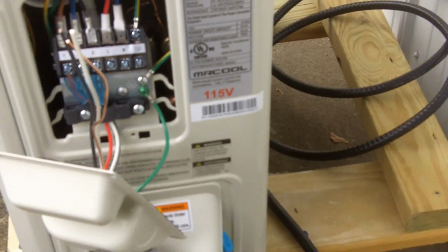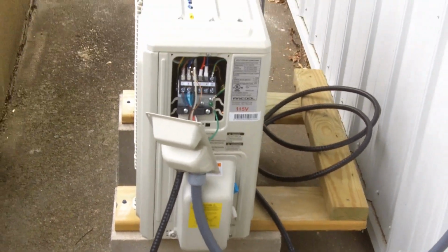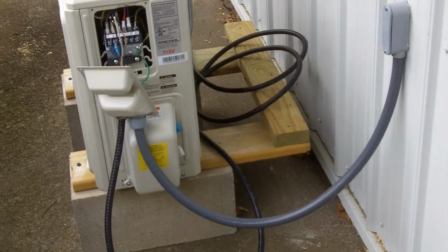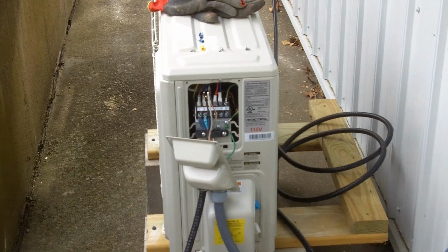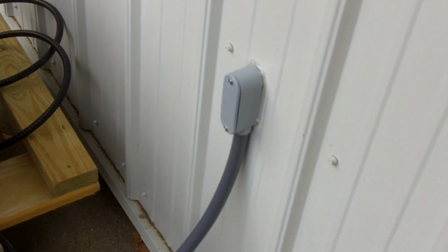You have to take off a green screw on the bottom right for your ground wire, and then the other 3 plug right in. Here I'm showing where the 2 conduit connectors come in - that's from the indoor unit, the green ground, and then there are numbers you can't really make out here, but 1, 2, 3. Make sure you're on 1, 2, and 3 corresponding with the indoor wires, which have 1, 2, 3 written on one side. Just make sure you plug those in.